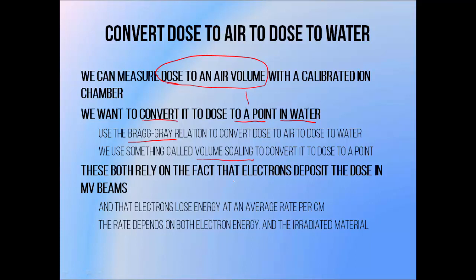The Bragg-Gray theory and volume scaling are often lumped together — in fact you don't often hear volume scaling talked about in the literature at all. Both of these processes only work under the same set of specific conditions, namely that secondary electrons are responsible for depositing the dose inside the ionisation chamber, which is true in high energy beams, and some others which I'm going to talk about in a moment.